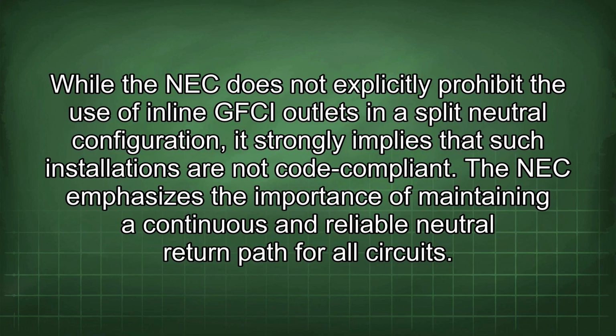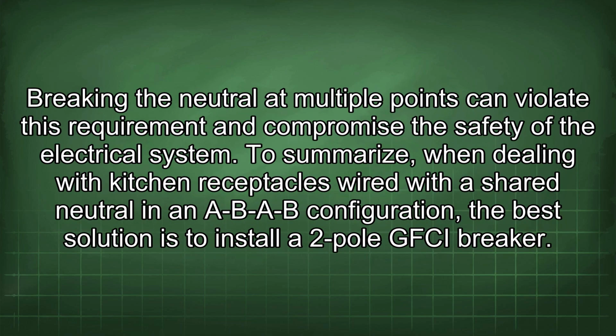While the NEC does not explicitly prohibit the use of inline GFCI outlets in a split-neutral configuration, it strongly implies that such installations are not code compliant. The NEC emphasizes the importance of maintaining a continuous and reliable neutral return path for all circuits. Breaking the neutral at multiple points can violate this requirement and compromise the safety of the electrical system.